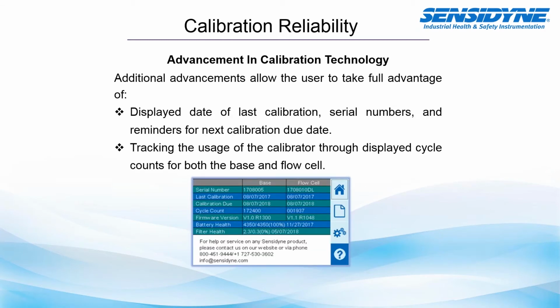It's important that your calibrator also provides specific information about the calibrator, and if it's a 2-piece calibrator, both the base and the flow cell: when it was last calibrated, when calibration is next due, if there are firmware versions or updates that could be involved, as well as whether it has good battery health or filter health, if your calibrator has such devices.